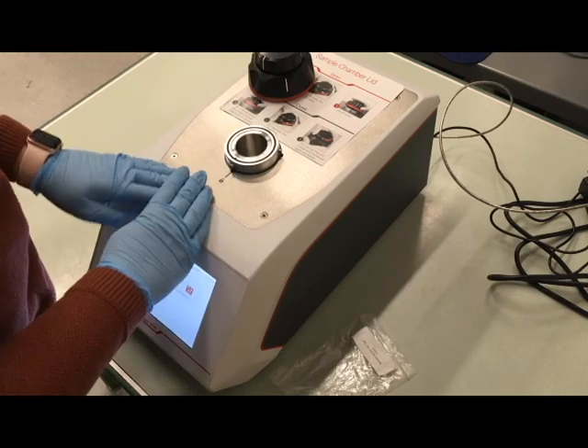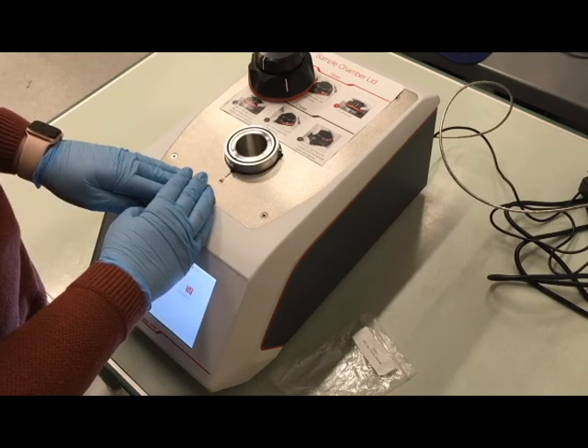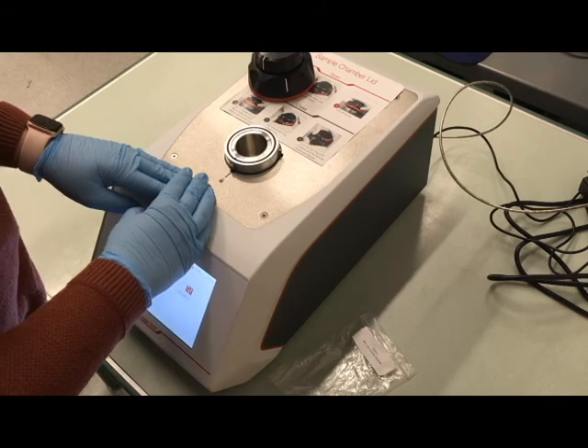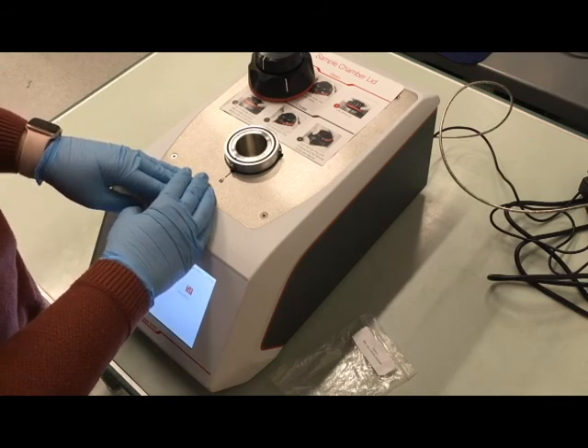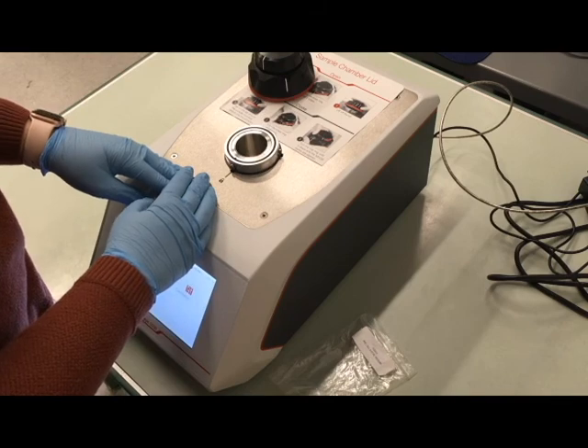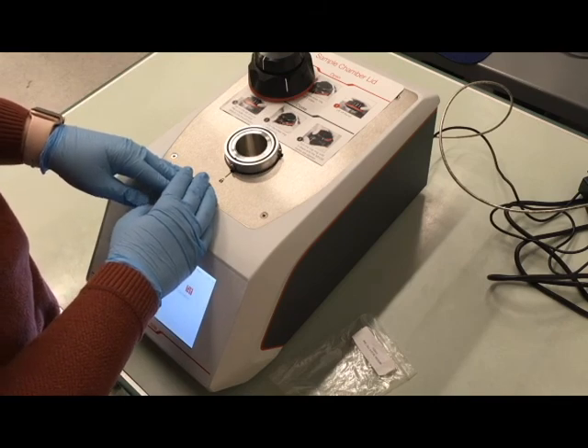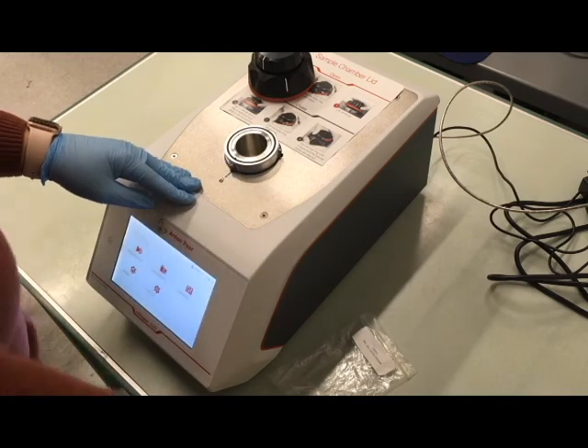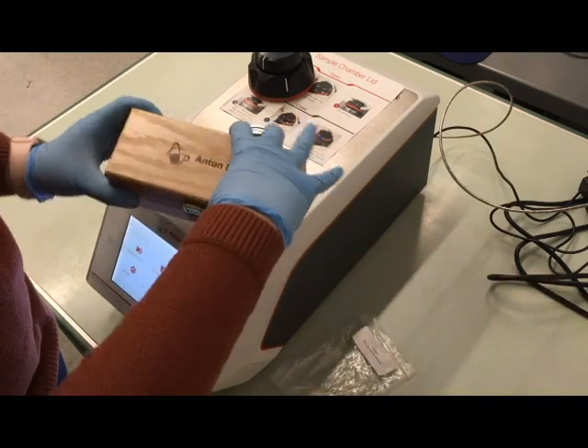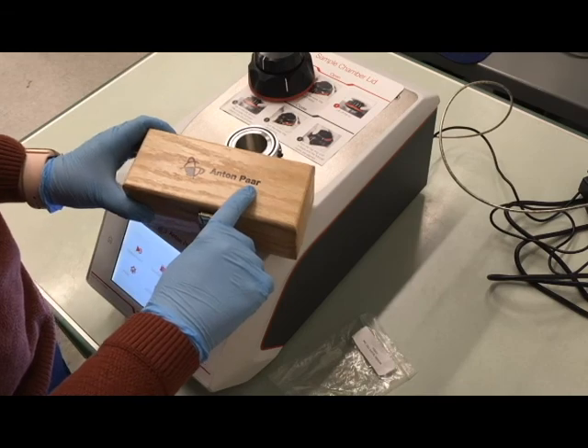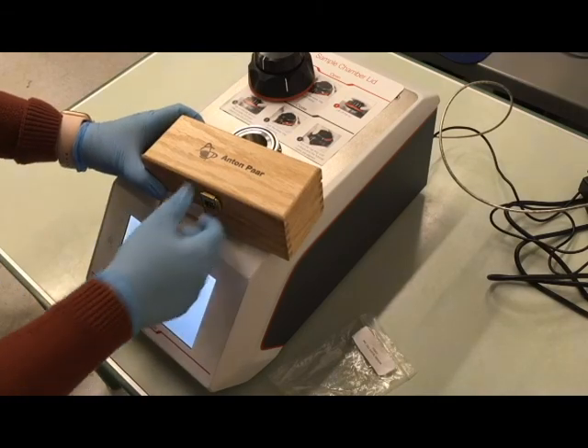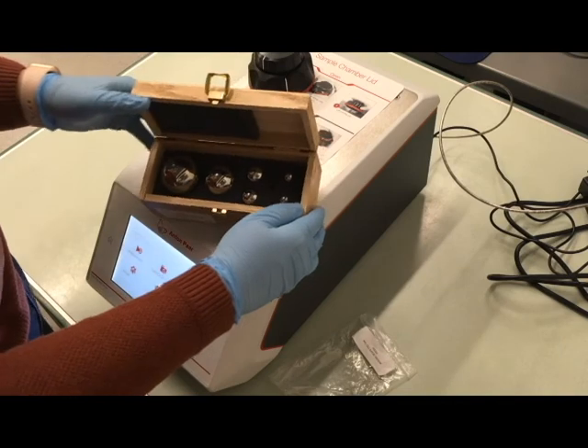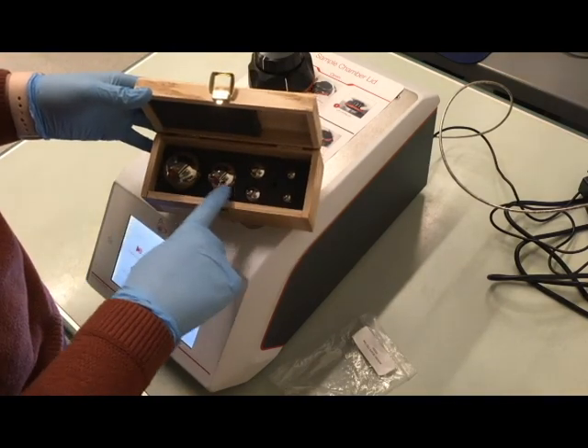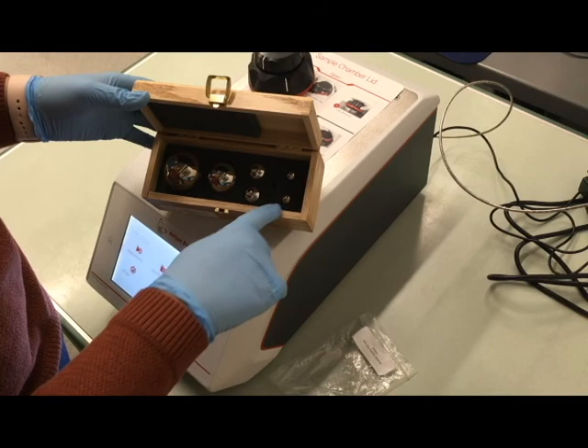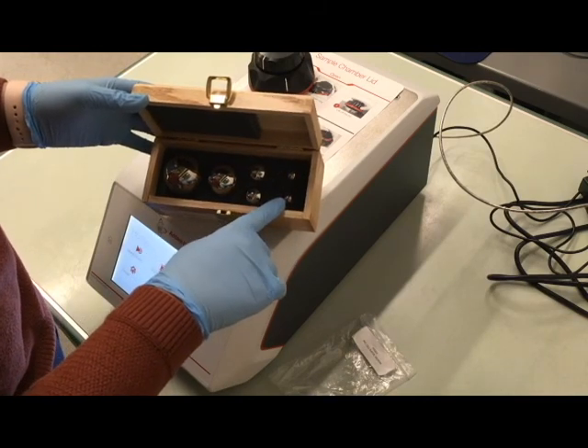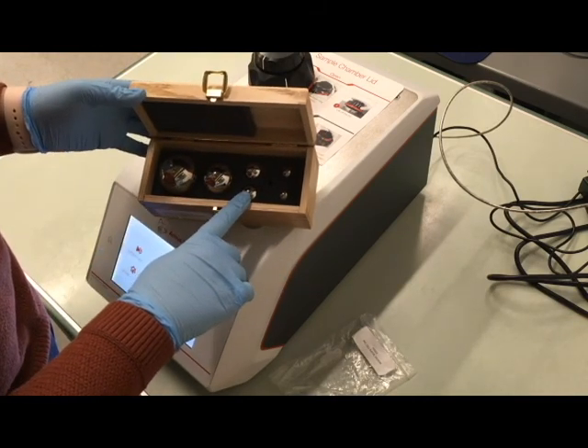When you first come to the machine, you're always going to run a calibration, meaning that we are going to use some spheres with a known volume and mass. We're going to run those first to ensure that the machine is running with good parameters. To the right of the machine is a box that says Anton Paar on the top, same as the machine itself. This box has a set of spheres: large, medium, small, and then micro, meso, and nano are these three right here. And we're going to use these to calibrate our instrument.